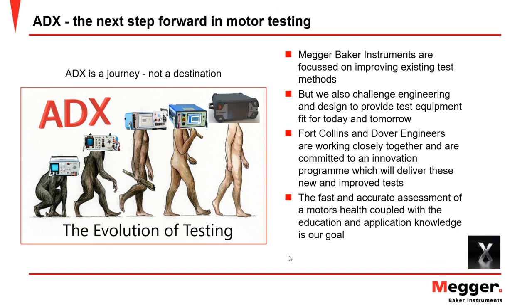Now, the reason why these test units are bigger than, let's just say, a handheld normal insulation resistance meter or a multimeter is because in the back there are capacitors. Some of the tests that we perform try to emulate the startup process of an electric motor. When an electric motor starts, the contactors come in, and just prior to them making contact, there's an arc. But they're heavily sprung, so the contactors close that gap as soon as possible. But in slow motion, there is always a gap, which leads to an arc in the contactor. That arc creates a spike, which can go through to the windings.